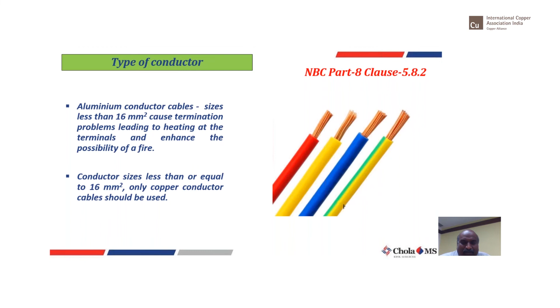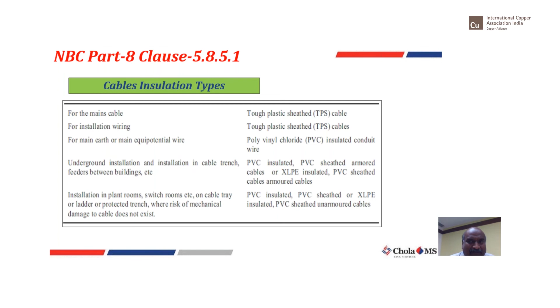NBC also talks about the type of insulation, such as XLPE and PVC; various types of insulation are there. So you need to decide what type of cable would be suitable for your environment. Environment plays a major role in deciding what type of cable you want to use. The internal conductor is one thing. Apart from that, the outer cable insulation also plays a role depending on the environment in which you are going to use those cables, which in turn will help in improving the life of the cable.